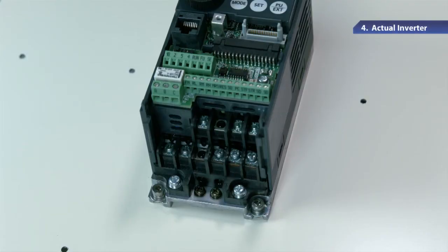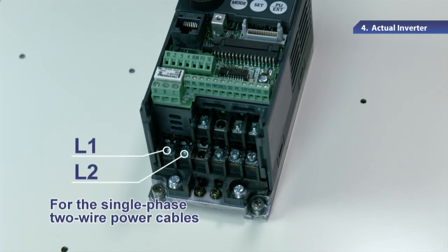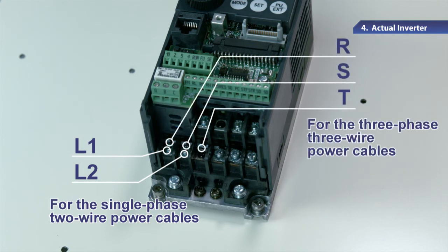First, please make sure the power is off. Then, connect the power cords to the inverter terminals. Connect the single-phase, two-wire power cables to the main circuit terminal L1 and L2. Connect the three-phase, three-wire power cables to the main circuit terminals R, S, and T.